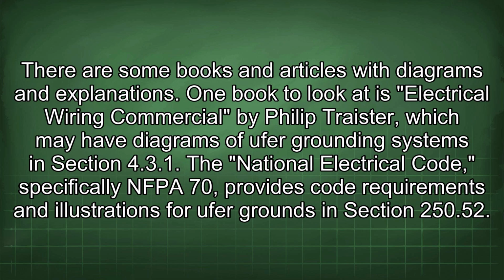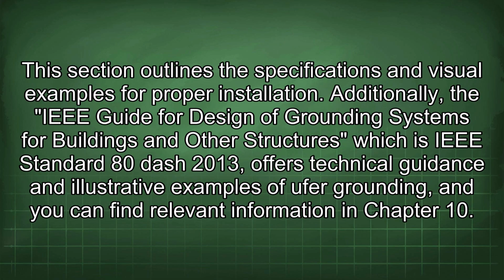There are some books and articles with diagrams and explanations. One book to look at is Electrical Wiring Commercial by Philip Traister, which may have diagrams of Ufer grounding systems in section 4.3.1. The National Electrical Code, specifically NFPA 70, provides code requirements and illustrations for Ufer grounds in section 250.52. This section outlines the specifications and visual examples for proper installation. Additionally, the IEEE Guide for Design of Grounding Systems for Buildings and Other Structures, which is IEEE Standard 80-2013, offers technical guidance and illustrative examples of Ufer grounding, and you can find relevant information in Chapter 10.